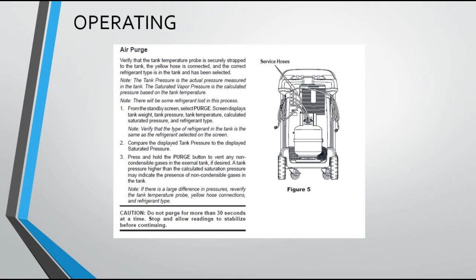Air purge: verify that the tank temperature probe is securely strapped to the tank, the yellow hose is connected, and the correct refrigerant type is in the tank and has been selected. Note: the tank pressure is the actual pressure measured in the tank. The saturated vapor pressure is the calculated pressure based on the tank temperature. Note: there will be some refrigerant lost in this process. 1. From the standby screen, select Purge.